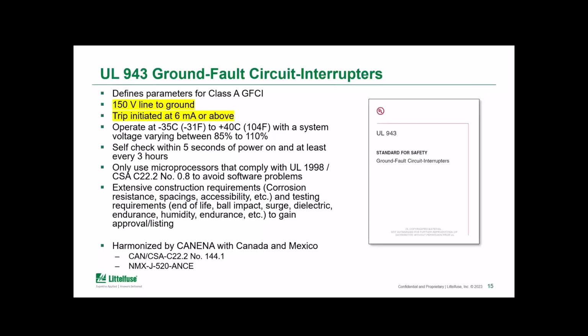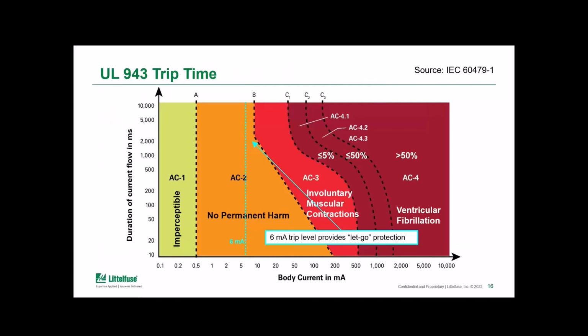So that is why you might hear people refer to GFCIs as a 3.5 milliamp or 4 milliamp or 5 milliamp device, but I'm going to use 6 milliamps for this presentation. So if we lay that trip level on that human risk curve, you can see that the 6 milliamp level of Class A is below the level of muscular contractions. So in other words, it's below the let go threshold.